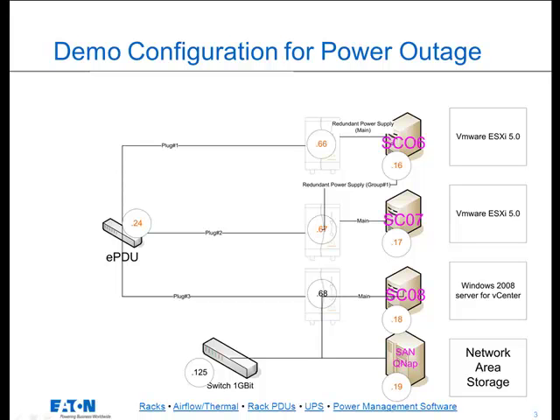In the demo, we have vCenter, two ESXi hosts, an Eaton UPS, and an Eaton EPDU. One of the ESXi servers is powered by the UPS, which is connected to an outlet on the EPDU. We demonstrate the installation of the IPM plug-in into vCenter and cause a power disruption by turning off the receptacle that powers the Eaton UPS.